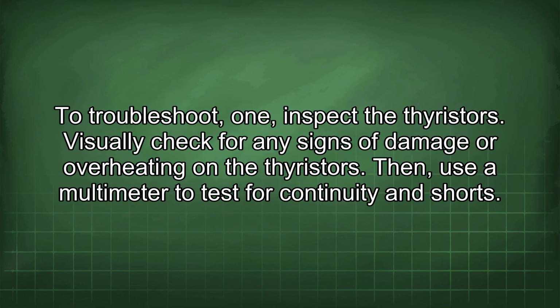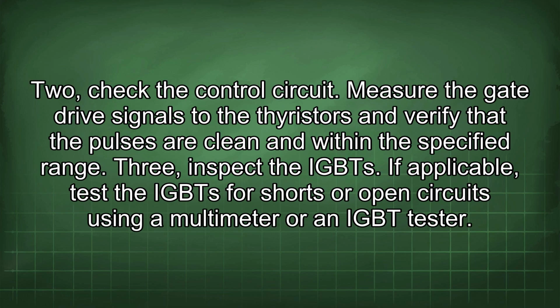To troubleshoot: 1. Inspect the thyristors. Visually check for any signs of damage or overheating on the thyristors. Then, use a multimeter to test for continuity and shorts. 2. Check the control circuit. Measure the gate drive signals to the thyristors and verify that the pulses are clean and within the specified range.